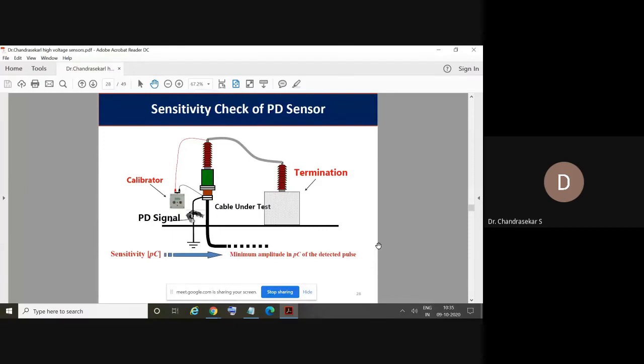So we started the work, and in the morning we started measuring PD, and at one particular junction we were continuously getting PD activities. But it was a new, fresh cable installed in that system, and we cannot expect any dielectric problem, leakage current or PD in a fresh cable. So we were really confused. What is this? Then after some time, when we moved away to other terminations, there was no problem, no signal at all. Completely lost.